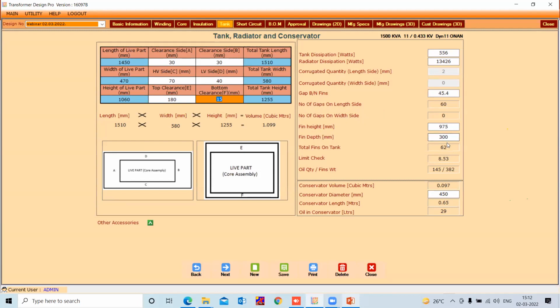Here the fins width and depth are editable, then the total number of fins on the tank, then the limit check functionality, then the oil quantity in fins and the fins weight. Thereafter, the conservator information: conservator volume, conservator diameter, length, and oil in conservator you will get over here. If you change the conservator diameter, your length will get changed automatically.